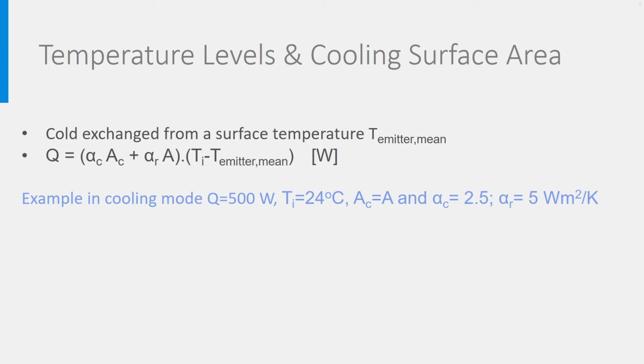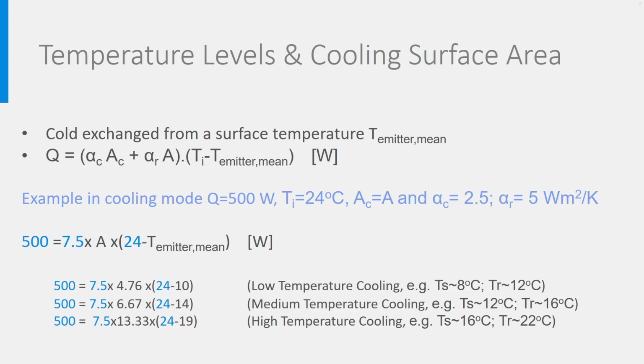In general, cooling panels have no additional convective surface and are essentially radiant, so we'll consider AC is equal to A. The heat transfer equation can therefore be rewritten as this, and here too we can choose different combinations of size A and average temperature T emitter mean of the cooling panels. In the first example, the panel has a temperature of 10 degrees Celsius. It is an average temperature. In fact, as an example, chilled water may enter the panel at 8 degrees and leave it at 12. Never mind, with this temperature, a panel surface area of 4.8 square meter is needed.